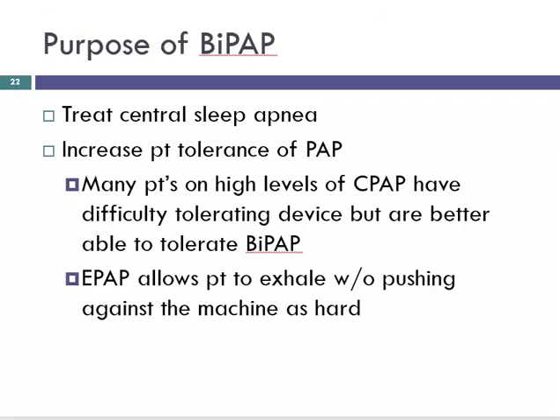BiPAP works well for patients that have central apneas because you can play around with that split between your inspiratory and expiratory pressure, and it can help initiate the breath if the patient were to fail to initiate the breath. If a patient doesn't tolerate CPAP, so once you get the CPAP pressure up to a certain level, it's standard for most labs to make the jump over to BiPAP. So with CPAP levels, we're talking like 15 and above, that's a lot of pressure to try to breathe out against. So most labs have standards in place to make the jump to BiPAP to make it more comfortable, and the patient is better able to tolerate it because they're not breathing out against such a high pressure.